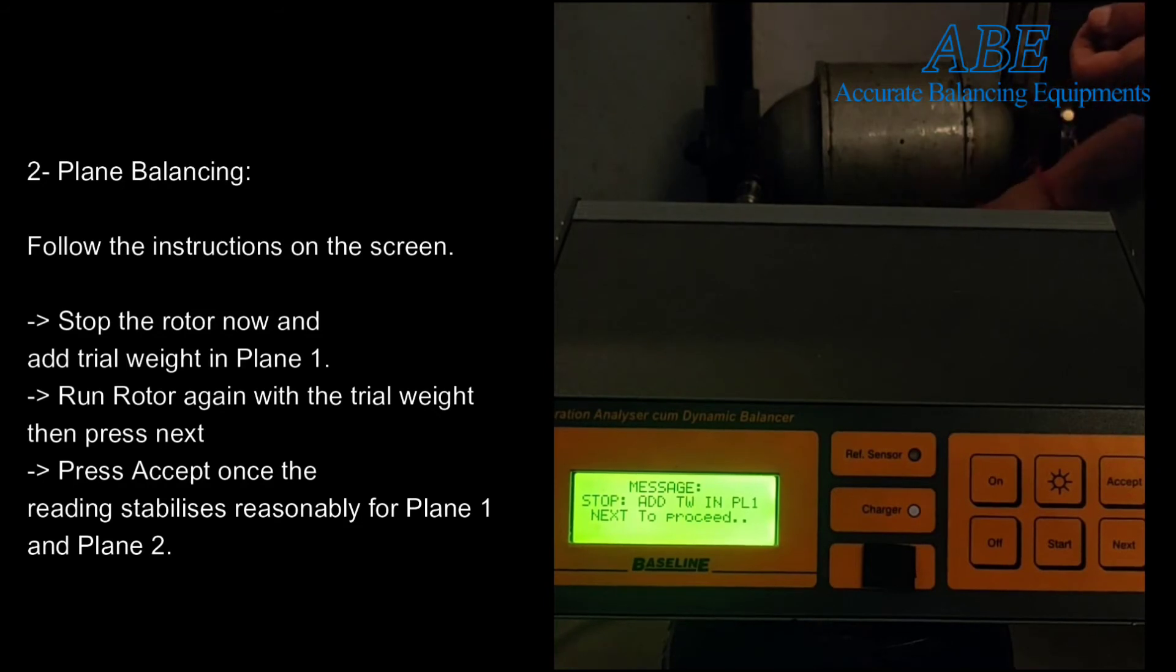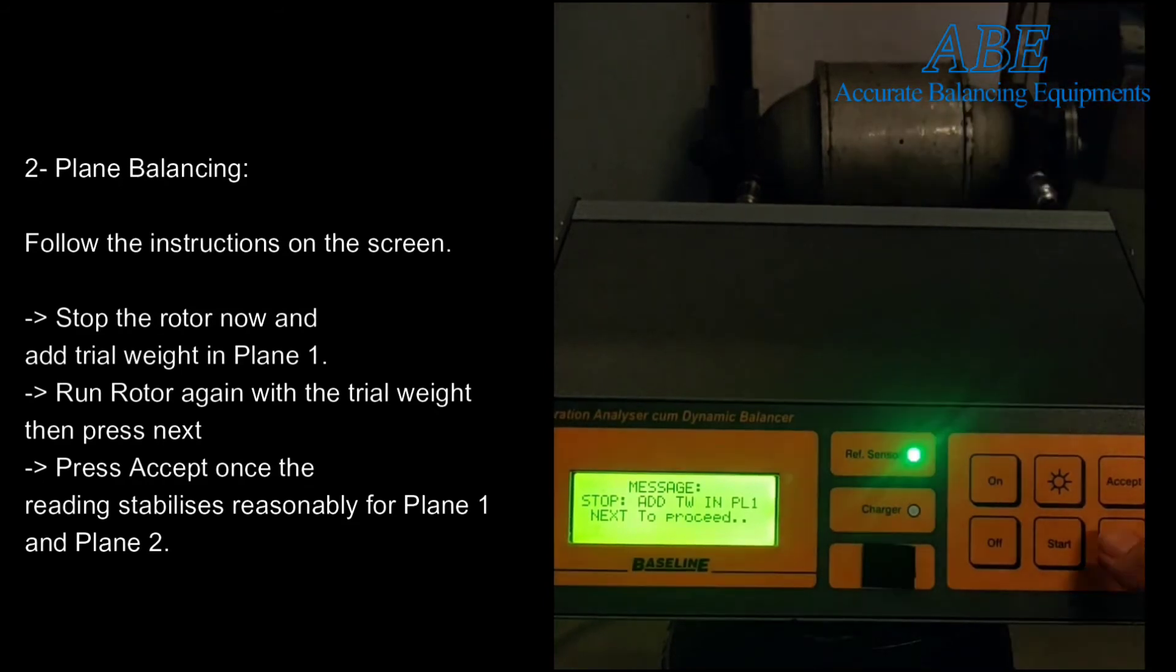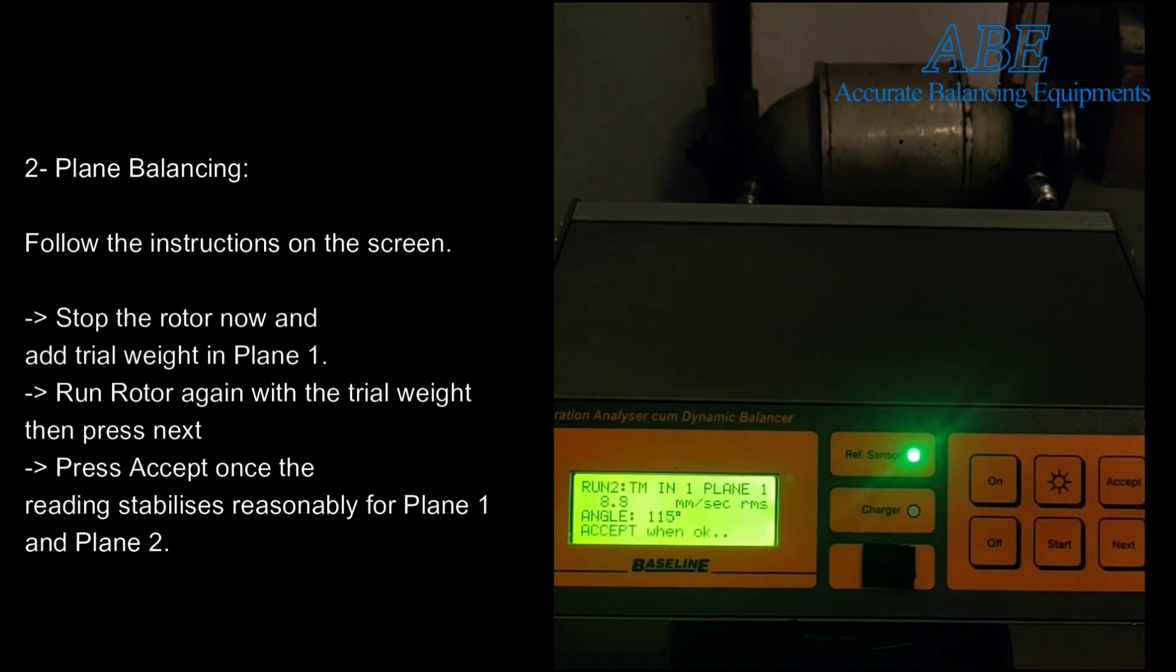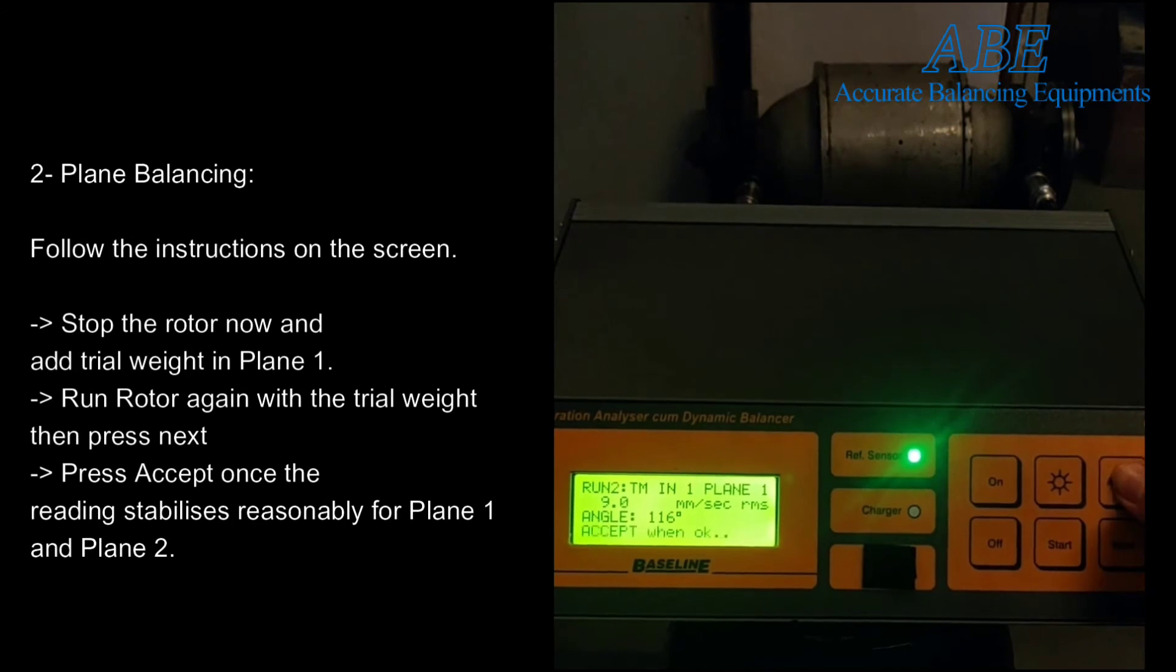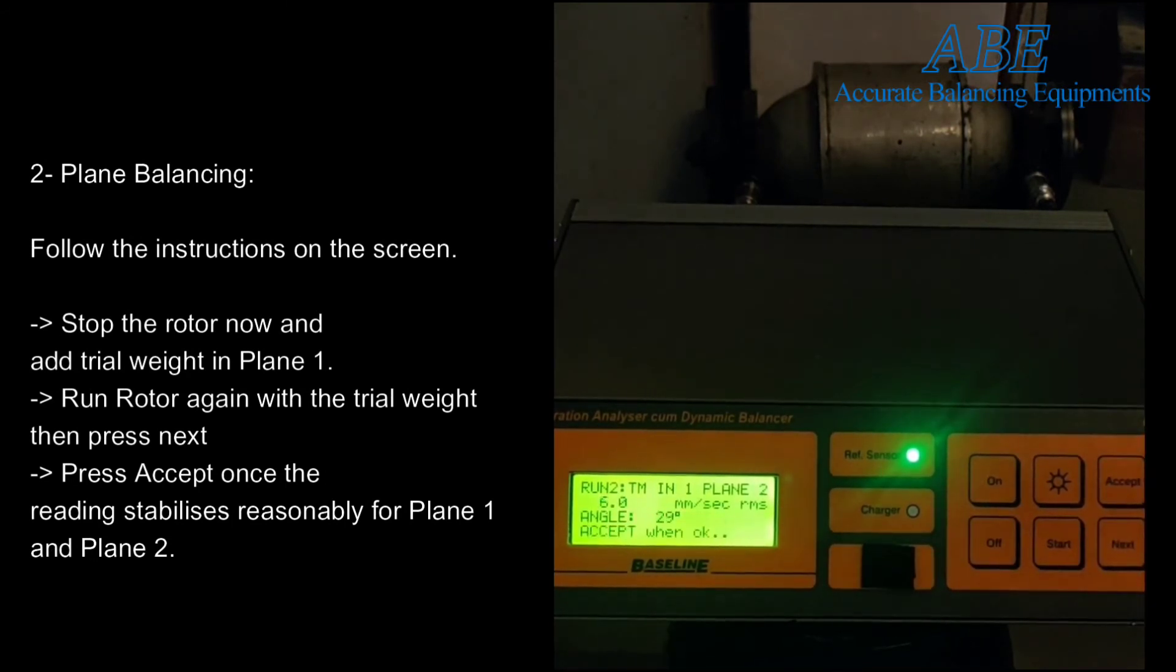After adding the trial weight in plane 1, run the rotor. The unit will then calculate vectors with the effect of the added trial weight in plane 1 and then in plane 2. After that, the unit will prompt you to stop the rotor. Remove the same trial weight from plane 1 and add it to plane 2. The unit will then calculate vectors for both the planes with the effect of the added trial weight in plane 2.